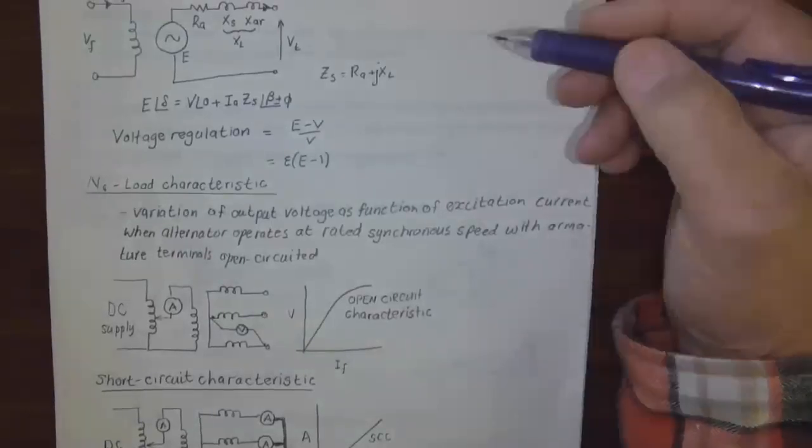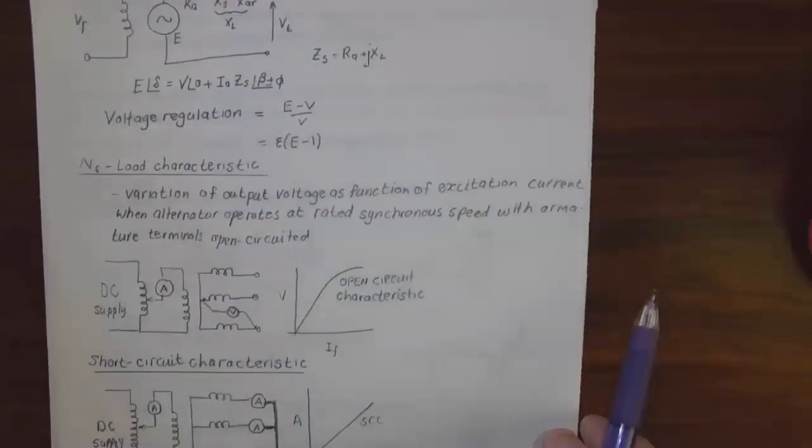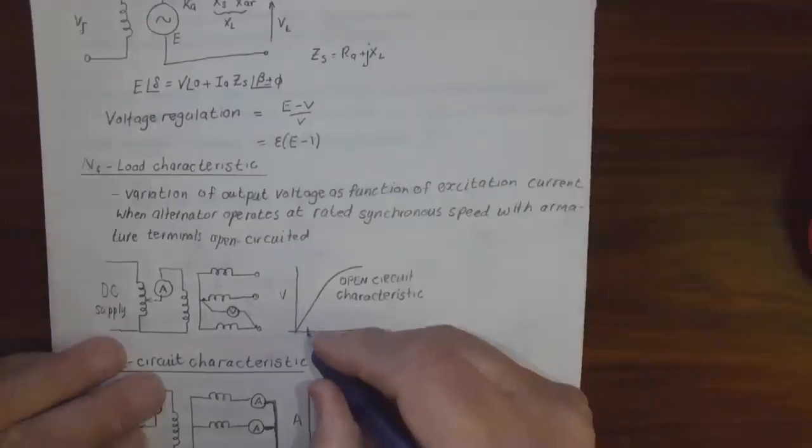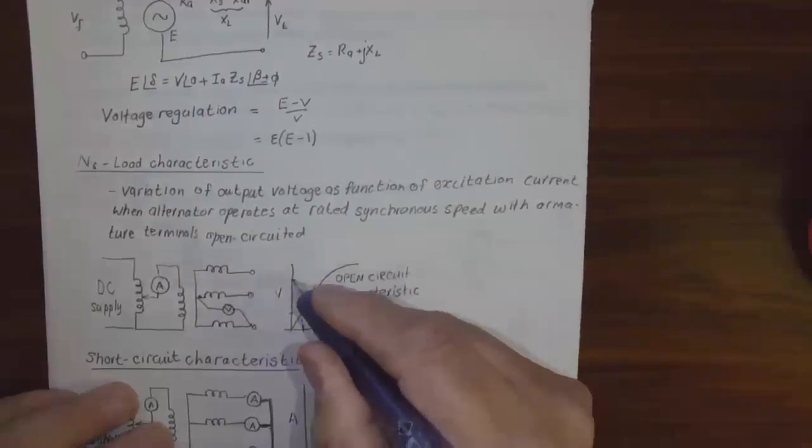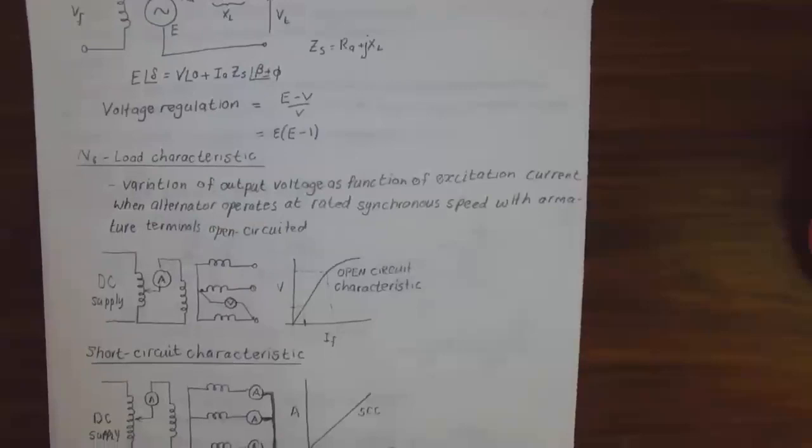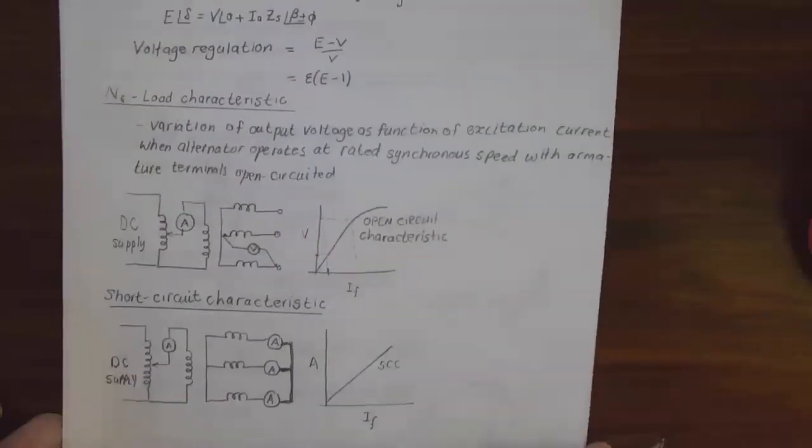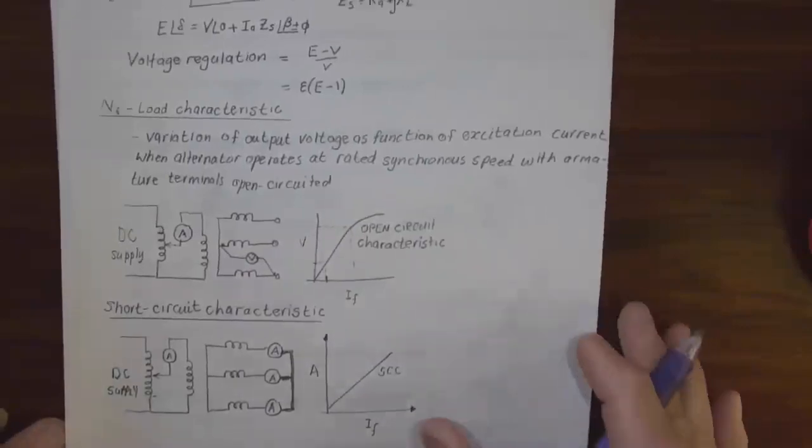The no load characteristic is a variation of the output voltage as a function of the excitation current when the alternator operates at rated speed with armature terminals open circuited. It's like the same as a DC machine: you've got your excitation current and the induced EMF for that specific current until you reach the end of your straight line, and then it becomes not constant anymore. The short circuit characteristic is with the terminal short circuit, machine running at synchronous speed. We start from zero with the excitation and increase it till maximum. So we've got armature current against the field current.